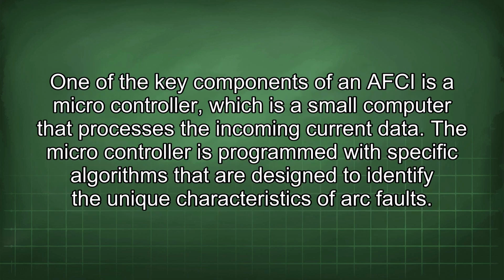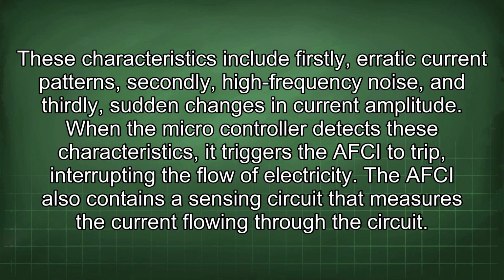One of the key components of an AFCI is a microcontroller, which is a small computer that processes the incoming current data. The microcontroller is programmed with specific algorithms that are designed to identify the unique characteristics of arc faults. These characteristics include, firstly, erratic current patterns, secondly, high-frequency noise, and thirdly, sudden changes in current amplitude. When the microcontroller detects these characteristics, it triggers the AFCI to trip, interrupting the flow of electricity.